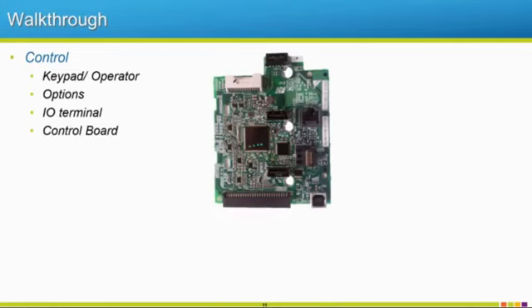Then we have our control board, so this is the brain of our drive. This tells the rest of my drive circuit when to fire the IGBTs, which we'll talk about a little later, or protect my motor, so observe current, or even protect my drive too. So this is where all those calculations are done.